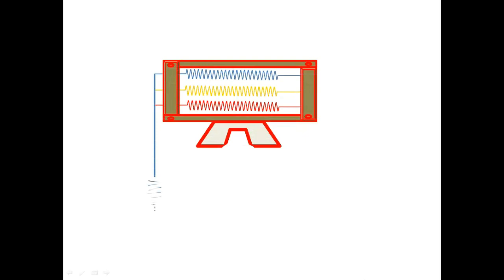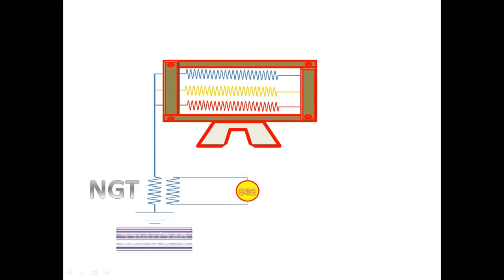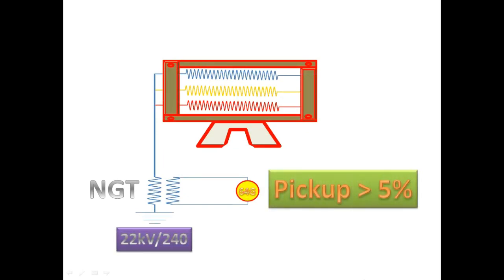In the generator, the neutral is connected with the neutral grounding transformer, and from that neutral grounding transformer we have a VT connection. The VT is connected to the relay for sensing fault, and this VT ratio is 22 kV over 240 volts.